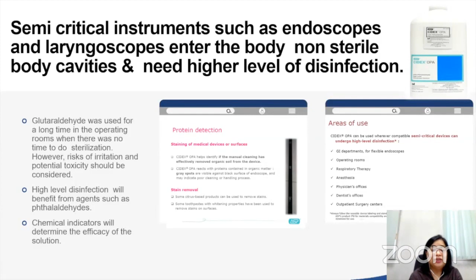The nice thing about the Cidex OPA is that, unlike the regular Cidex where you just soak for 30 minutes and then take it out, Cidex OPA has chemical indicators, so you can determine the efficacy of the solution after use. You can use these solutions in the ORs, in the GI departments, particularly for the endoscopes, and in any healthcare setting where you need a higher level of disinfection without necessarily having to do sterilization.